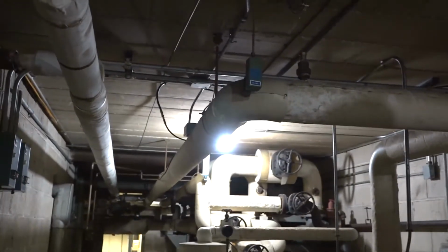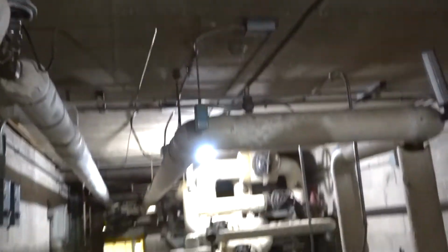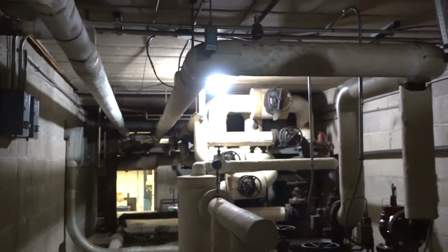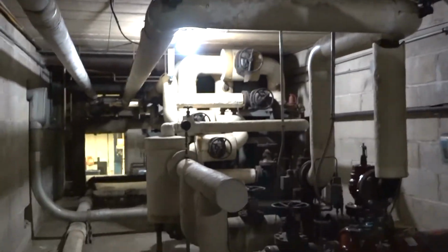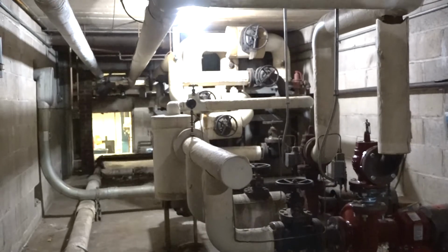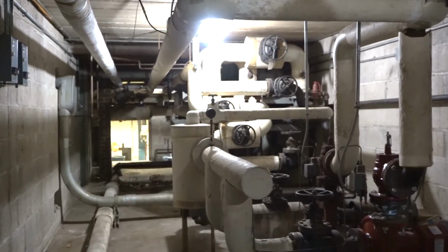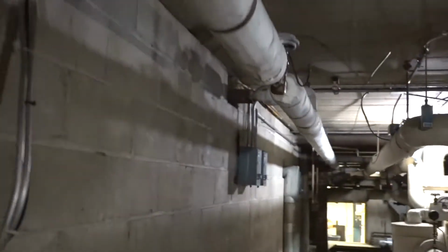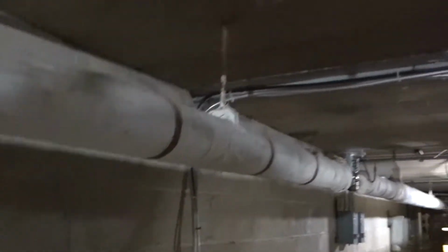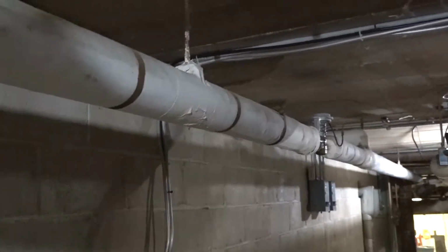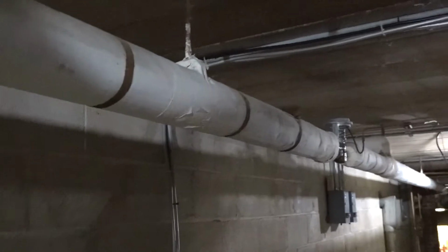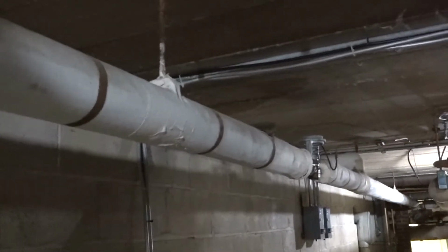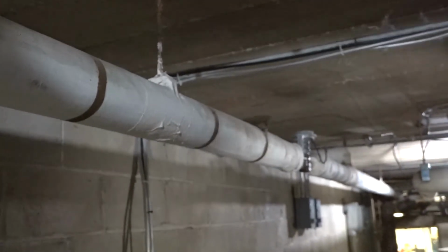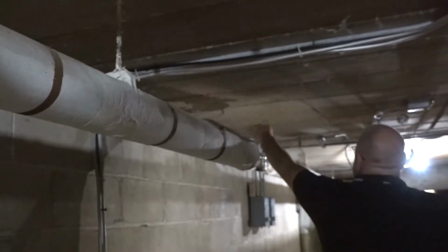The current standard in the new building, I assume, is all digital controls, yes? It's all DDC control, right? Yeah. So these are literally tubes through which vacuum or whatever has to flow to every point. It's just air. And they don't have a lot of feedback. No, you can't see what's going on with this, other than if the room is too hot or too cold. First thing you do is come down and check this here. A lot of times the diaphragm that's up in the top dry rots and leaks, then the room overheats.